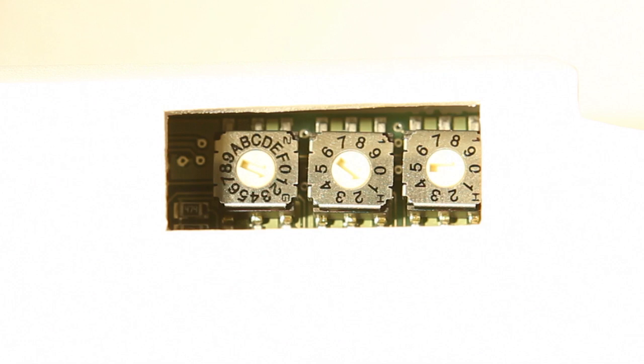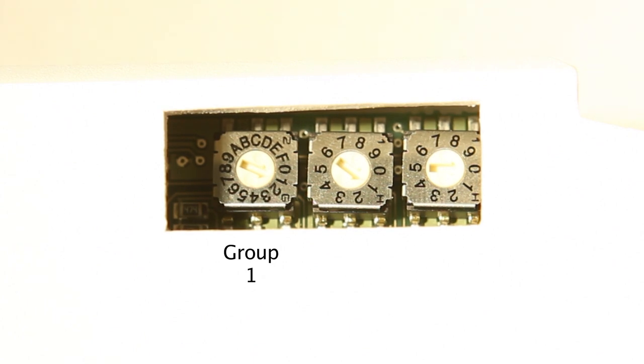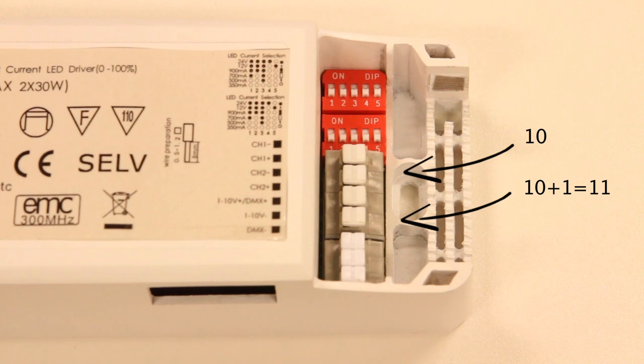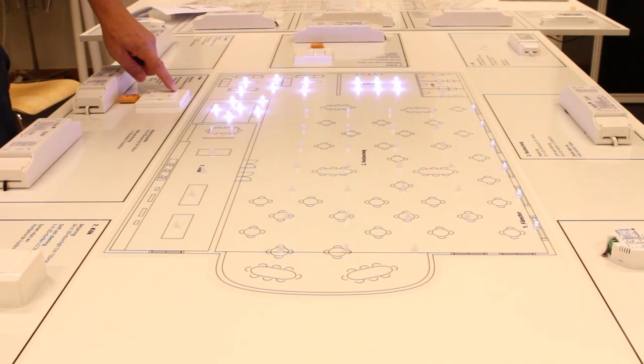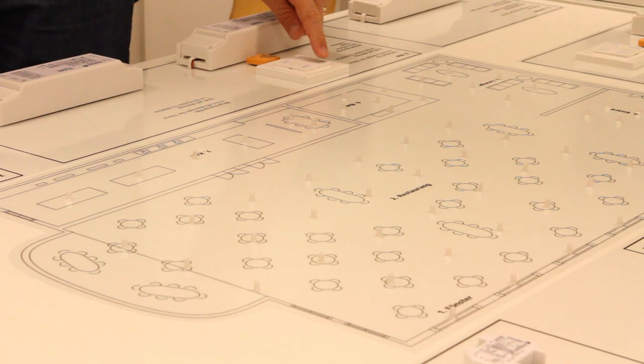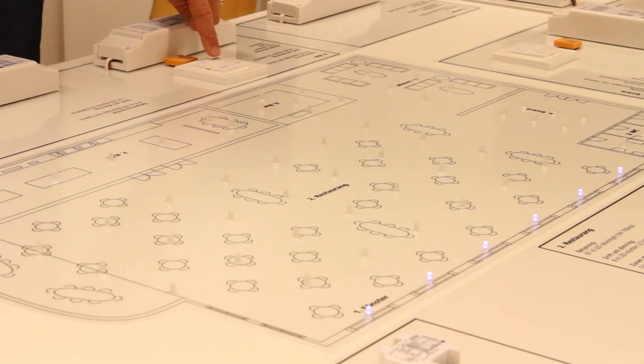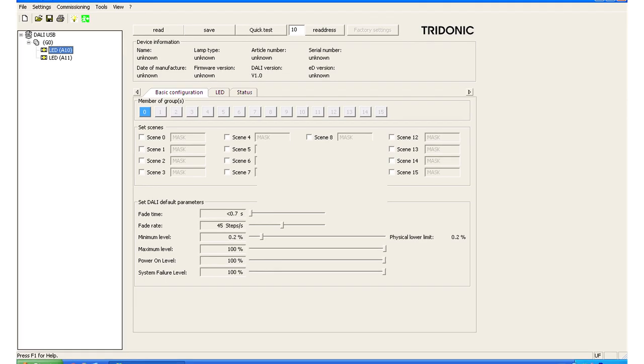In order to control several units together in a group, you must also set the group to which the LED control gear must belong. If you want the LED control gear to belong to group 1, set the first rotary switch to 1. Now the LED control gear belongs to group 1, and output 1 has address 10 and output 2 has address 11. If address 10 is controlled, the only output that responds is number 1. If group number 1 is controlled, output number 1 and 2 will react simultaneously. If there are several LED control gears set to the same group, all LED control gears are controlled simultaneously. All addressing and grouping can also be done from a computer if desired.